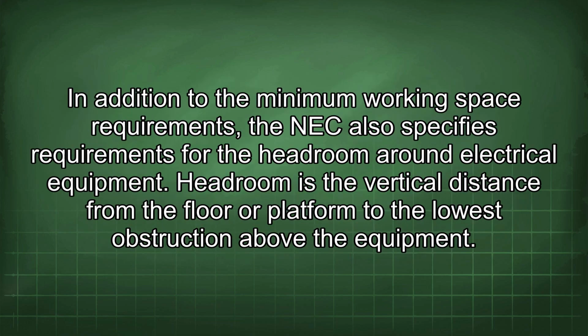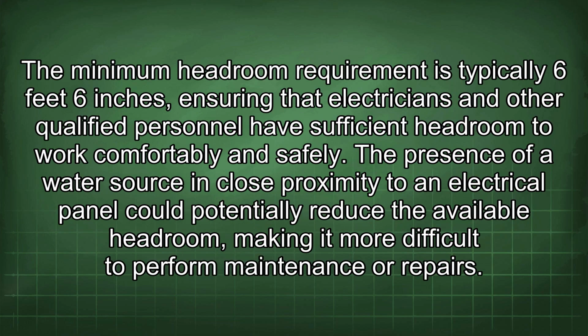In addition to the minimum working space requirements, the NEC also specifies requirements for headroom around electrical equipment. Headroom is the vertical distance from the floor or platform to the lowest obstruction above the equipment. The minimum headroom requirement is typically 6 feet 6 inches, ensuring electricians and other qualified personnel have sufficient headroom to work comfortably and safely. The presence of a water source in close proximity to an electrical panel could potentially reduce the available headroom, making it more difficult to perform maintenance or repairs.